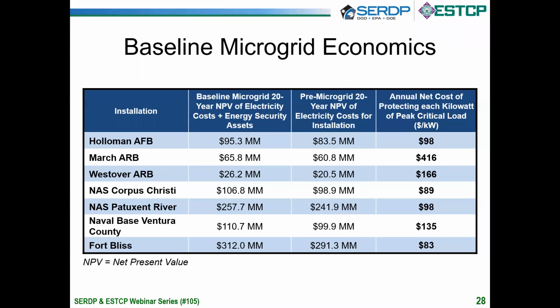With a critical load of 5,996 kilowatts, just about 6 megawatts at Holloman, that comes out to $585,000 per year, just multiplying the critical load times $98. That's also the difference between the middle 2 columns in this chart divided by 20 years. It's the difference between the electricity costs without the microgrid and with all the microgrid elements added.